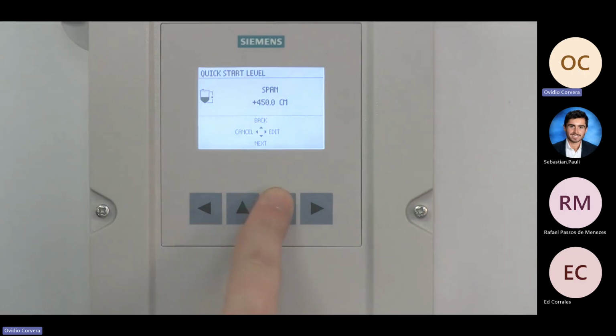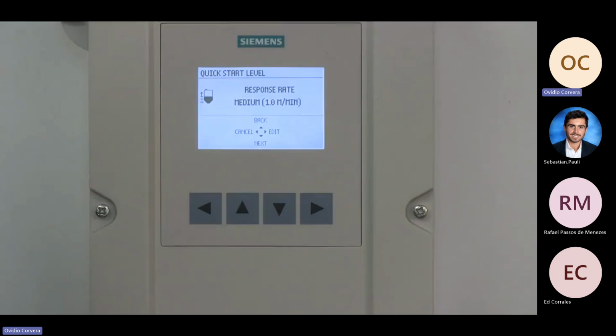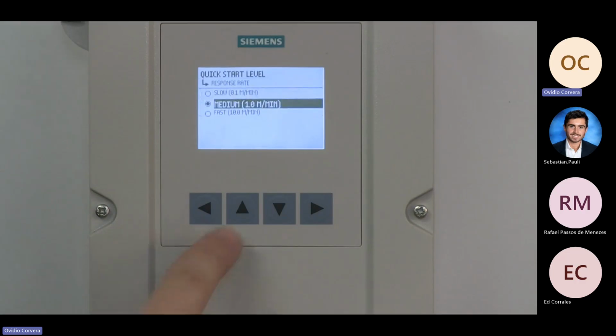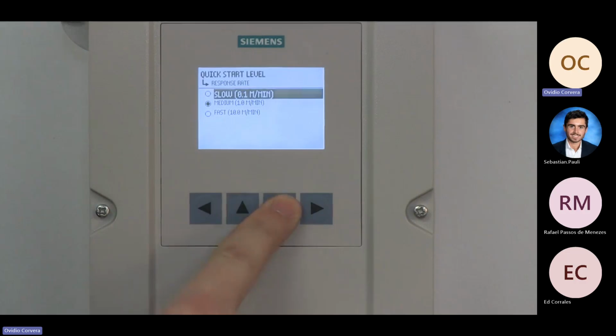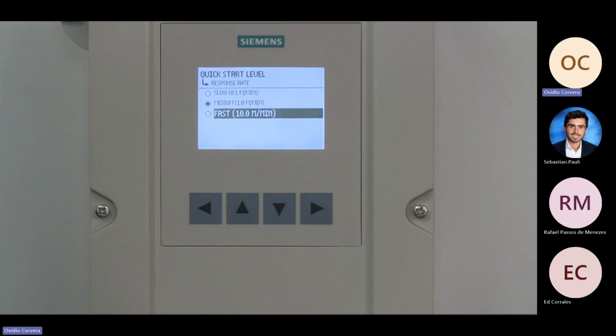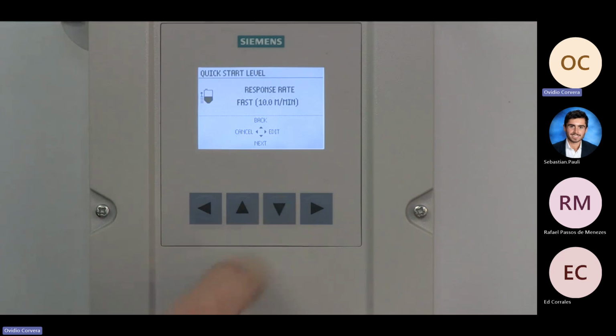The next step is to set the reaction speed of the device. The factory response rate default is set to medium, which is a rate of level change less than 1 meter in 1 minute. Press the right arrow to select Edit to modify this value. There are 3 options for speed of response: slow, medium, and fast. Your response rate should be set slightly higher than the maximum process response change. Using the up or down arrows, highlight your response rate and press the right arrow to enter your selection. Press the down arrow to select Next to proceed.